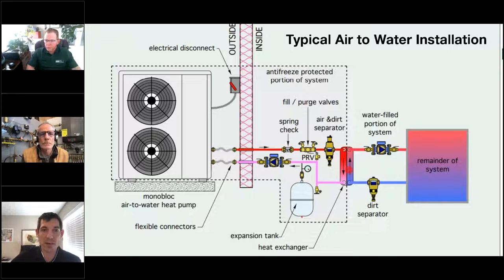The less glycol percentage-wise that we need, the better, because then we don't have to upsize our pumps. And the only thing that we like about glycol is that it doesn't freeze, so it's not fun to get air out of or to deal with in a system. And the flat plate right there lets you say, okay, we're just doing the heavy load of glycol on the left, and then on the right we're doing water because we're in Toronto, or if we're further north, then we're going to do a lower percentage of glycol for the rest of the system, so that blue pump on the right side may come down a size or two, which would be great.